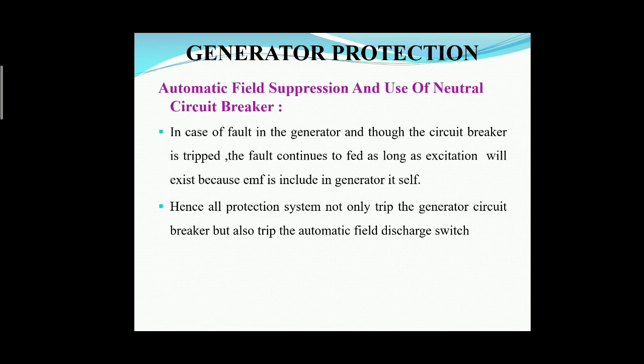If any fault is obtained in the generator and the circuit breaker is tripped, the fault continues to be fed as long as the excitation exists, because EMF is induced in the generator itself due to the presence of the fault.